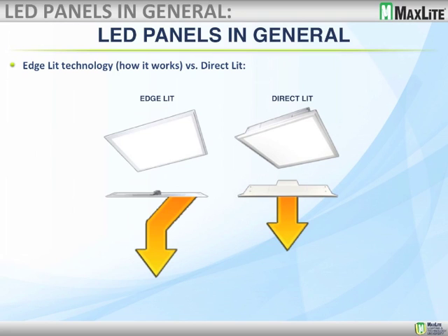There are two distinct types of light throw in LED troffer applications: direct-lit and edge-lit. With direct-lit, the LEDs are mounted in the back of the fixture to the PC boards with thermal heat sinks, and the LEDs point directly to the floor from the ceiling. With edge-lit, the LEDs are around the perimeter pointing towards each other, and a light guide pushes the light downward so that the whole panel is evenly illuminated with no hot or cold spots in either technology.